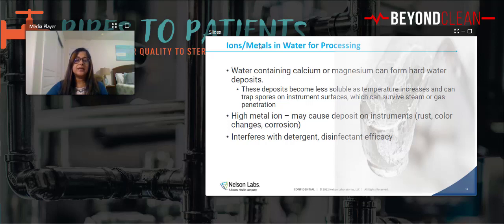One thing to remember is that heavy metals also interfere with detergent and disinfection efficacy - very important to remember that it affects how detergents work. Detergents have their own chemicals in them. Now add all these heavy metals in there - what happens? They bind with those chemicals, and when they bind with them, they make the detergent ineffective. And if it's ineffective, what's the point of the detergent? You might as well just rinse it with water at that point. So you want to make sure you're using the right quality of water to make these detergents as well.